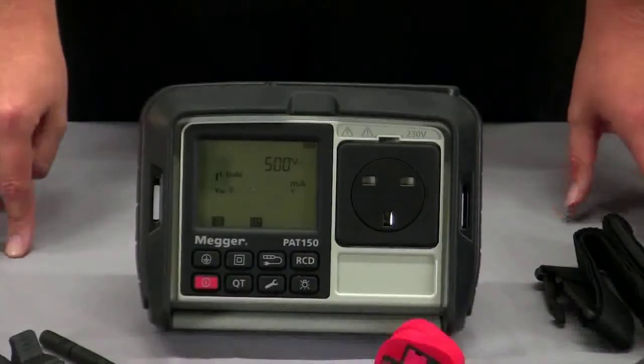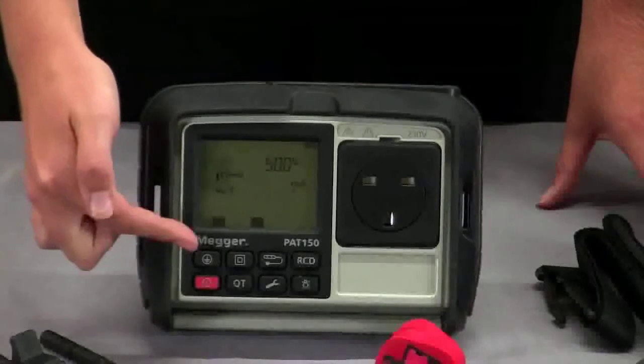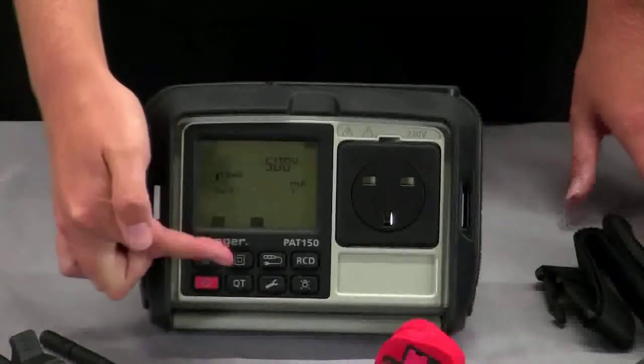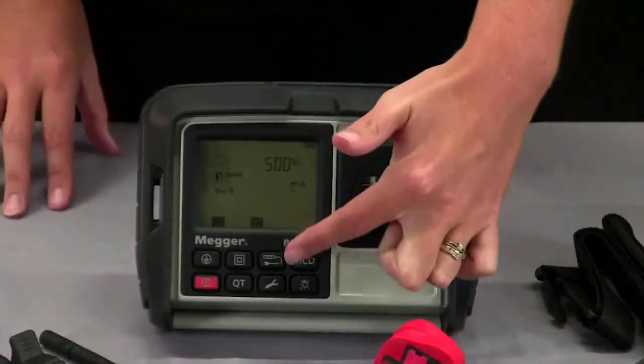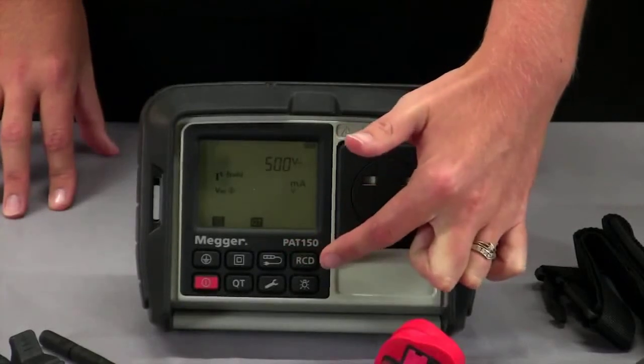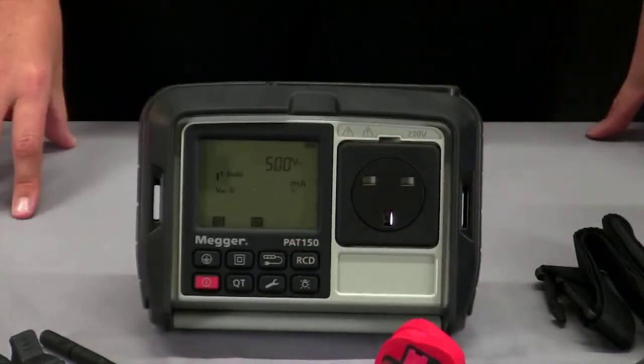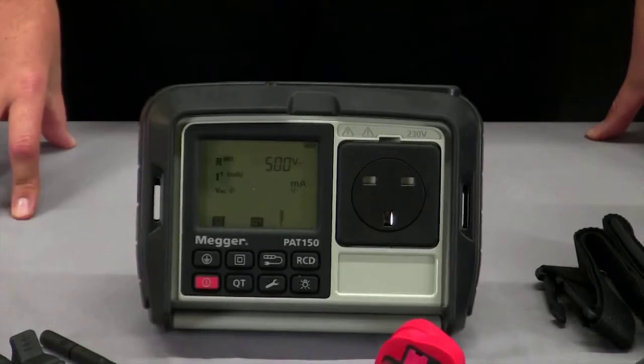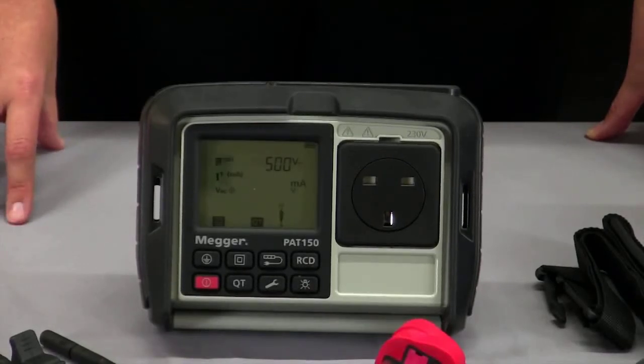The PAT150 gives you the capability of testing Class 1 earthed equipment, Class 2 double insulated equipment, extension leads and portable RCDs in a fully automated test mode. Alternatively, use the quick test facility to manually perform individual tests such as insulation resistance or earth continuity.